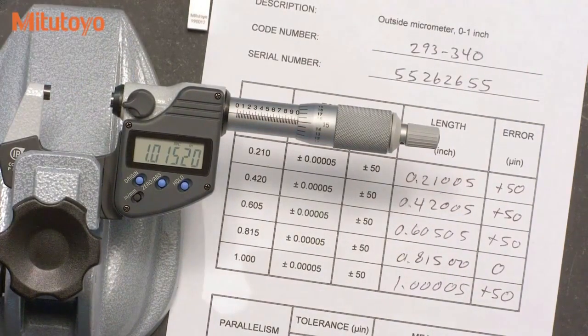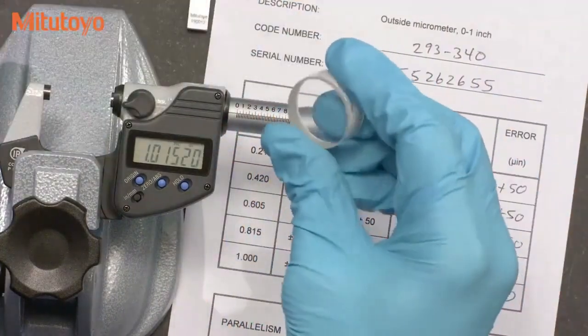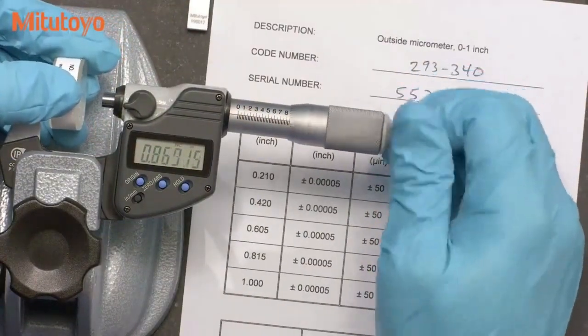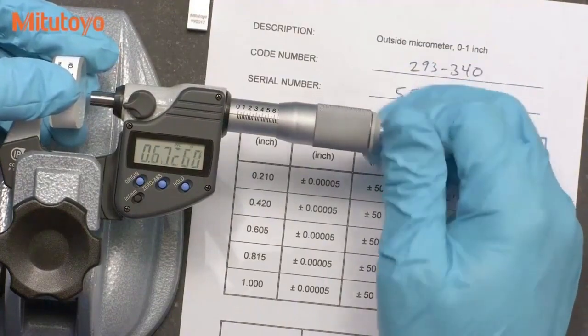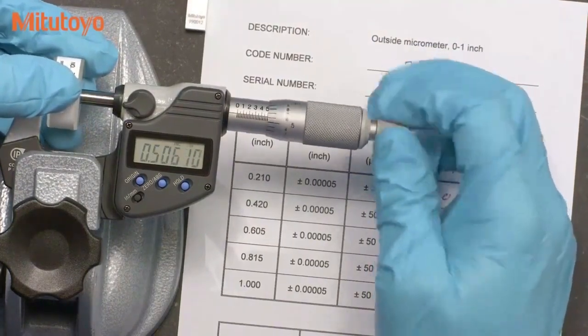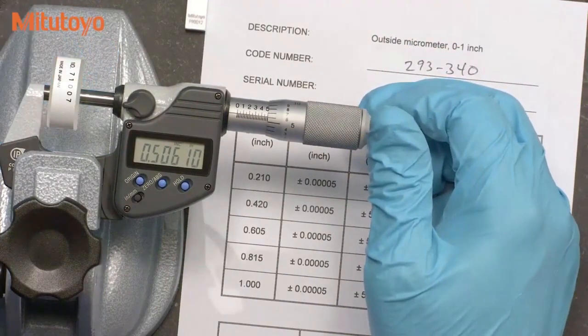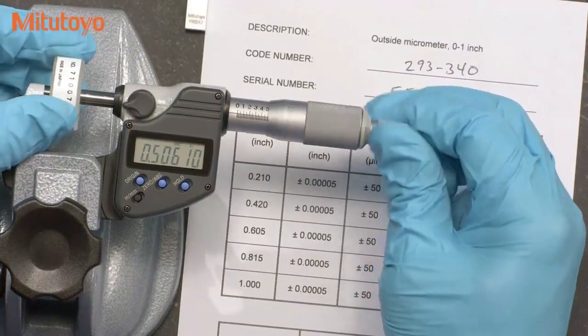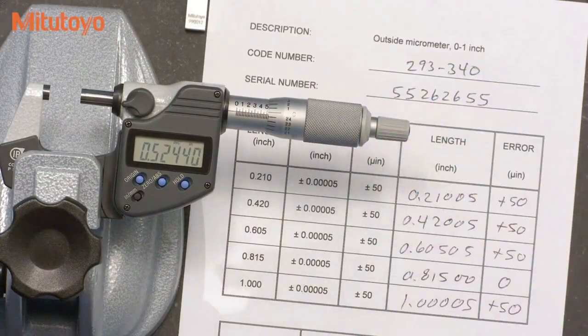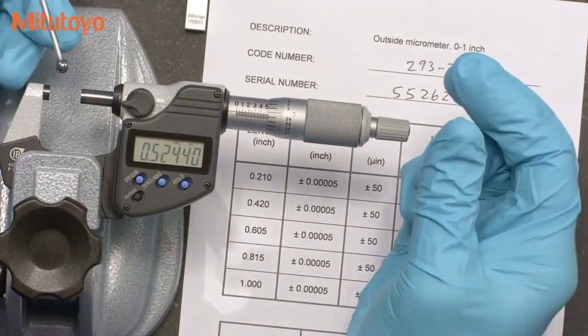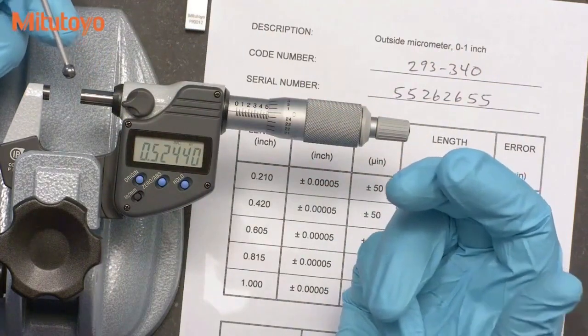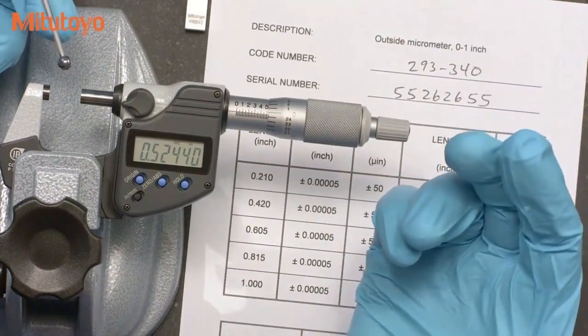Historically, the flatness and parallelism was checked using an optical parallel, like this. Now, this method is a bit cumbersome and requires some special skills in reading optical fringe patterns. So, instead of checking the micrometer in this manner, the ASME B89.1.13 standard presents a much simpler method. The reference standard that we'll use instead of the optical flat and parallel is a small sphere, like this ball gauge here. You can also use a stylus from a coordinate measuring machine if you'd like.